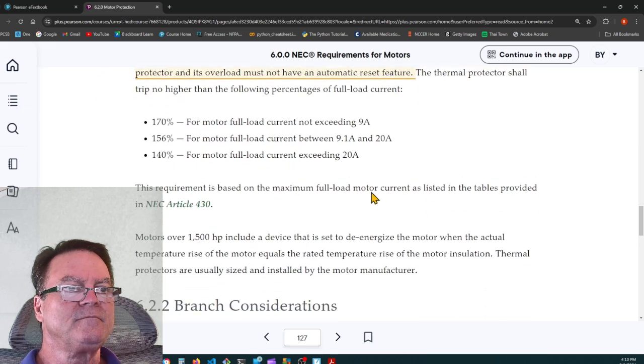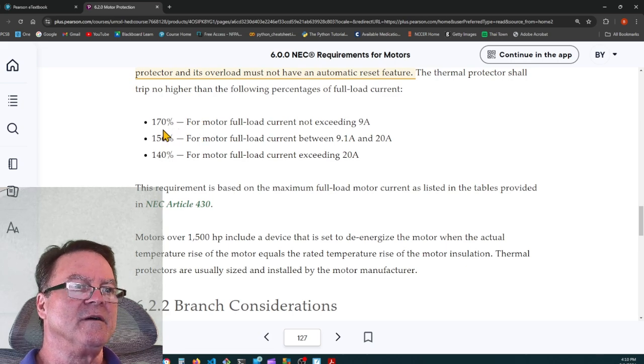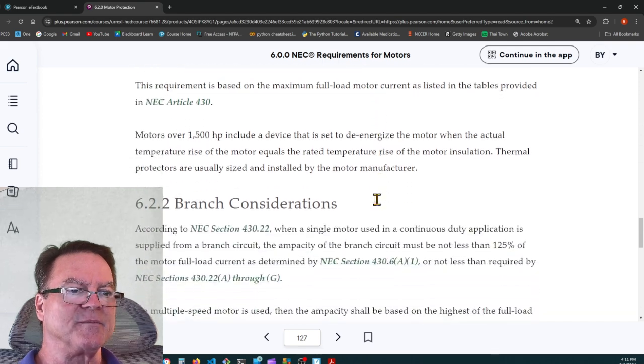And here it's 170% for full load current not exceeding 9 amps, 156% for full load current between 9.1 and 20 amps, and 140% of the motor full load current exceeding 20 amps.